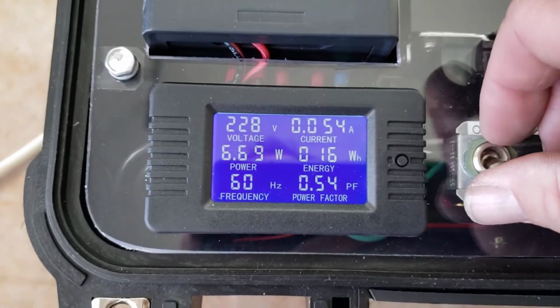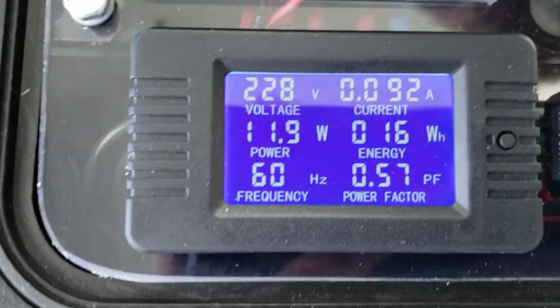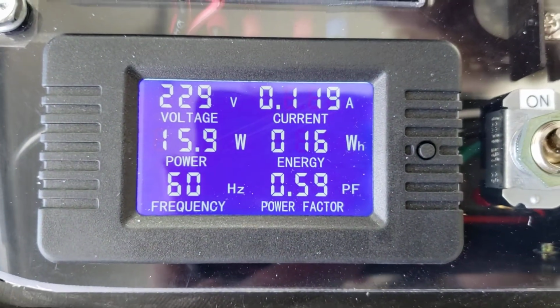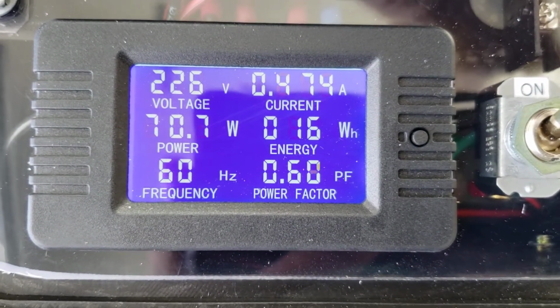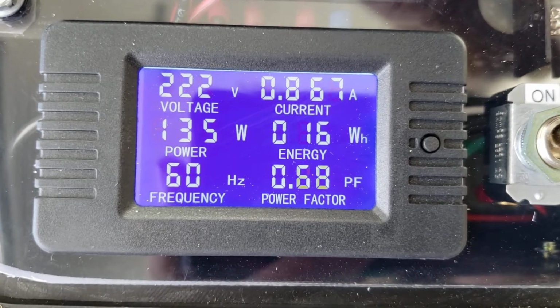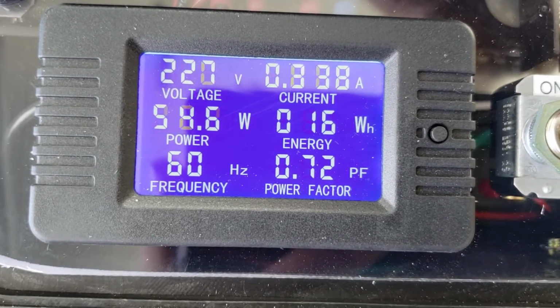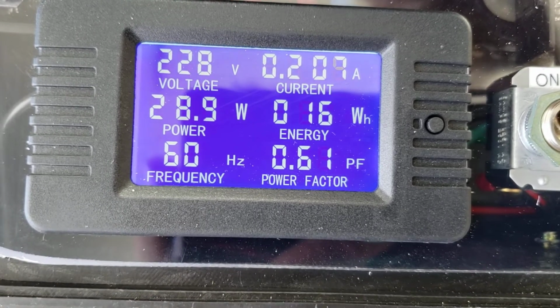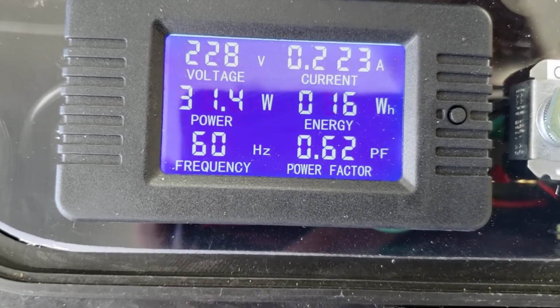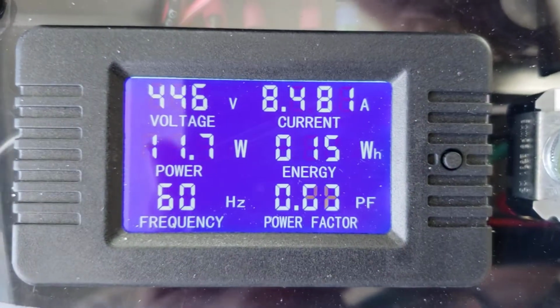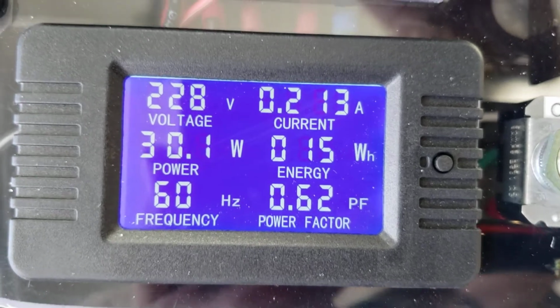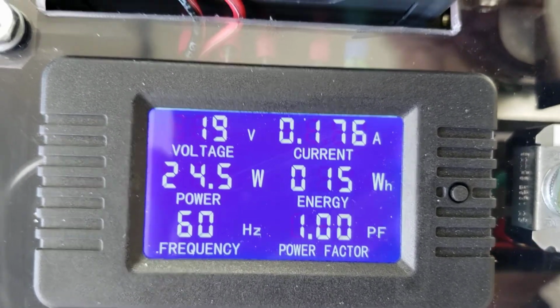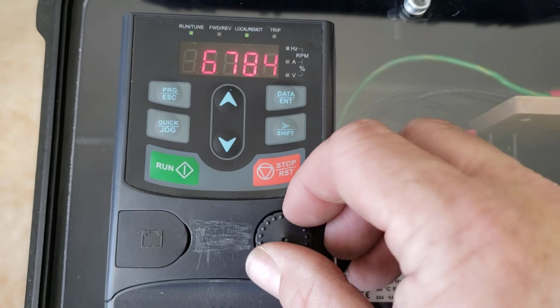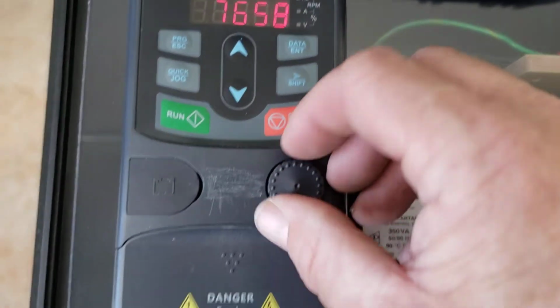Now, you don't normally see the display reset like it did on that last test, but occasionally with the arcing you get some abnormal transients and arcing. I'll try it again. You hear that one, and the screen just reset again. That's just the inductive interference causing that screen to reset. Yeah, the frequency is all over the place. It definitely doesn't like that cell, and that's how you would tell the difference.